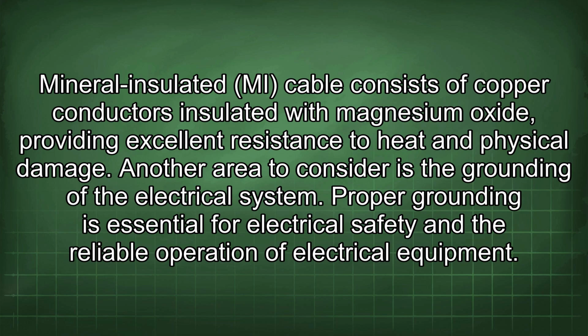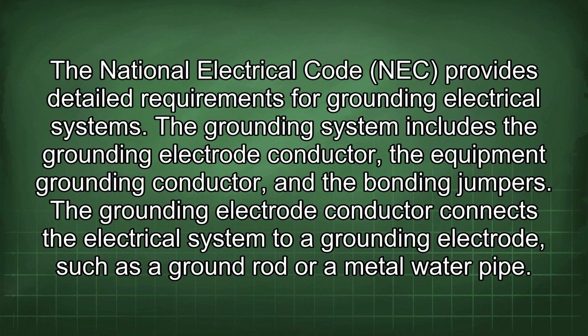Another area to consider is the grounding of the electrical system. Proper grounding is essential for electrical safety and the reliable operation of electrical equipment. The National Electrical Code (NEC) provides detailed requirements for grounding electrical systems. The grounding system includes the grounding electrode conductor, the equipment grounding conductor, and the bonding jumpers. The grounding electrode conductor connects the electrical system to a grounding electrode, such as a ground rod or a metal water pipe.